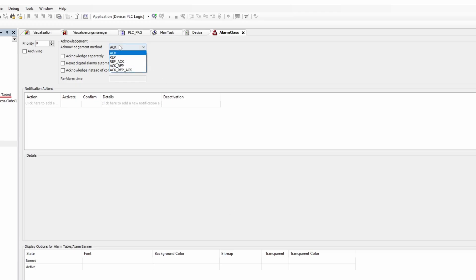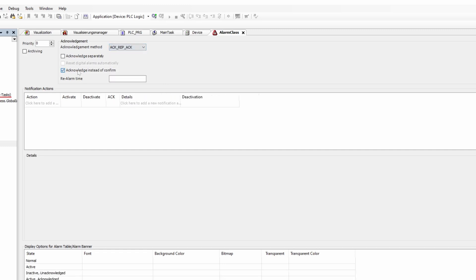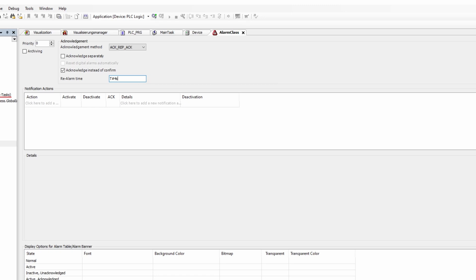There are several improvements in alarm management. A confirmation comment for the alarm table, OPC UA compliant, is now supported, with the comment and user ID being saved in the alarm history. Alarms can be re-triggered after a certain time and digital alarms can be automatically reset after acknowledgement. The separation of alarm detection and alarm processing enables fast alarm detection at the end of an application task.